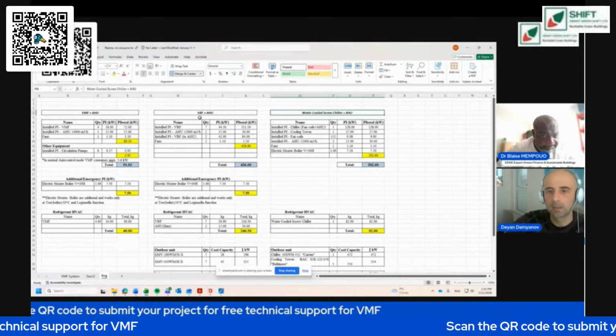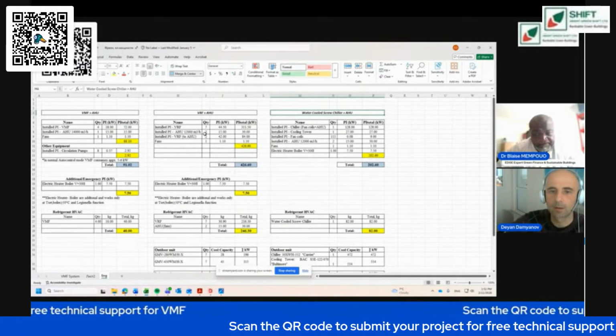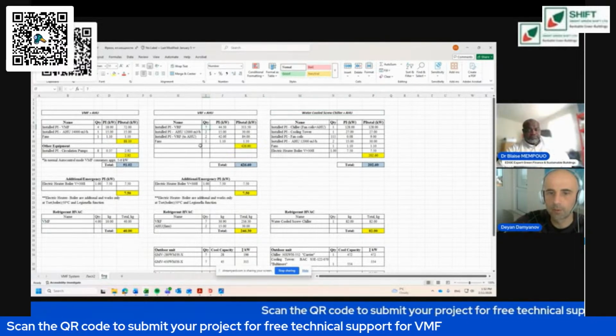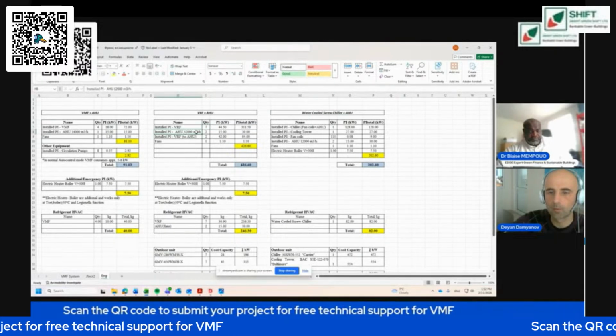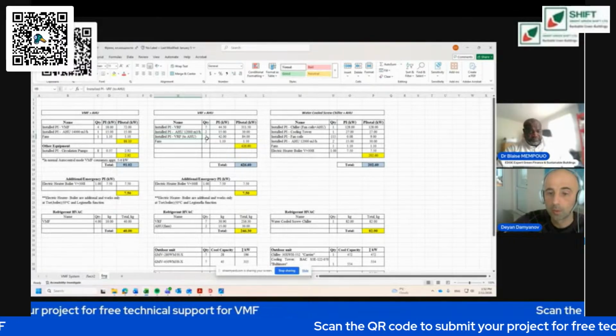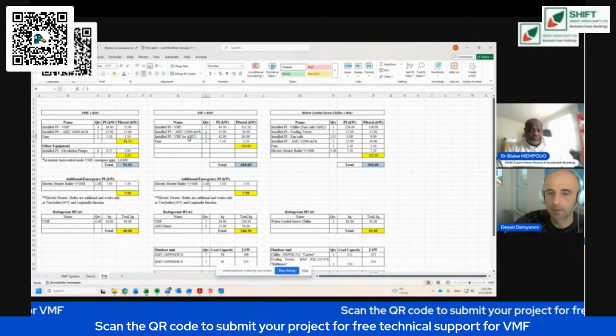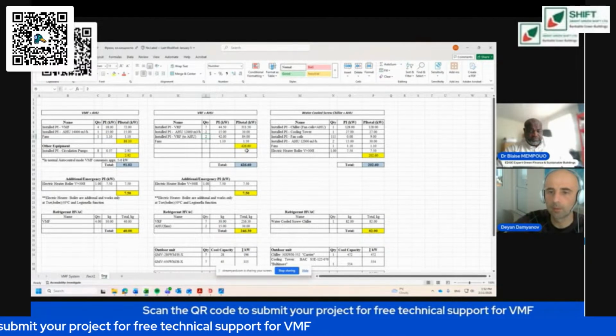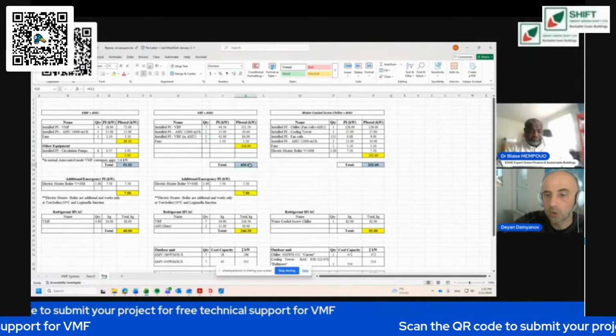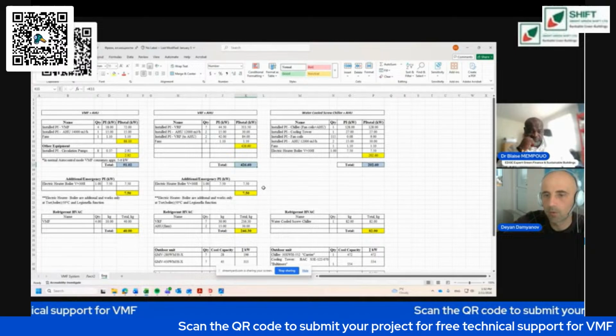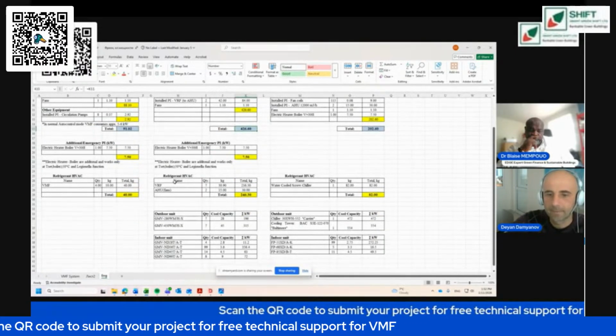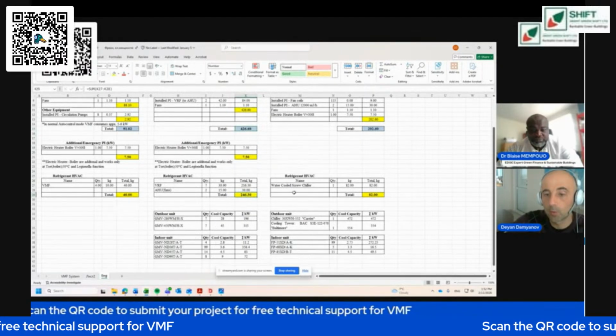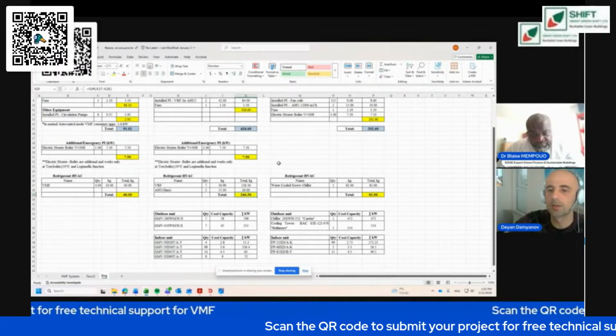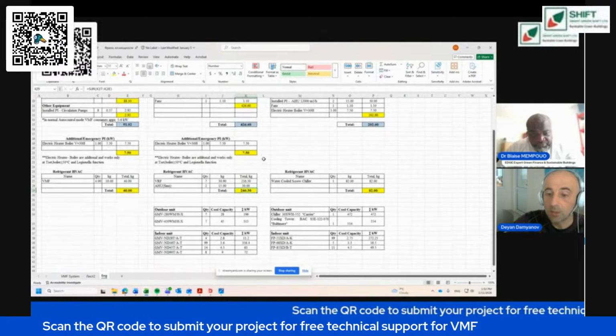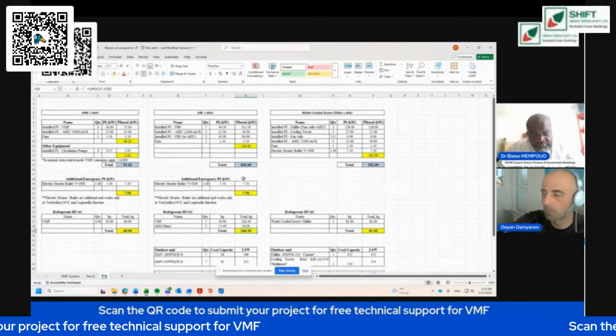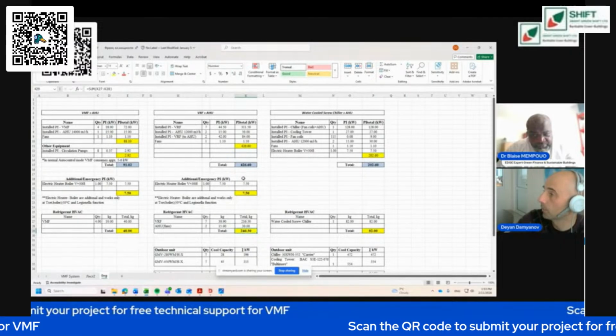In the original design, there are 7 external VRF units. We have the installed power for 2 air handling units, plus an additional 2 external VRF units supplying cold water or cold refrigerant for the air handling unit. The total installed electric power for this project is 426 kilowatts. We calculated the approximate quantity of refrigerant for this project at nearly 246 kilograms — that's very important, because a big part of this refrigerant quantity is inside the building in every single room.